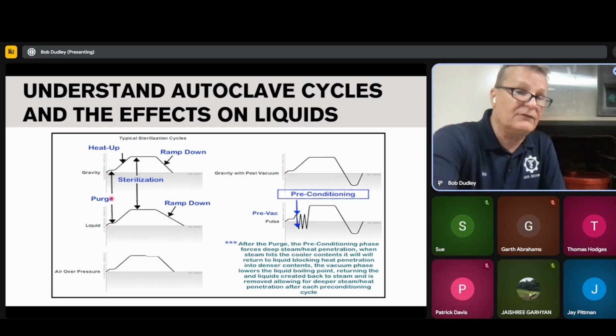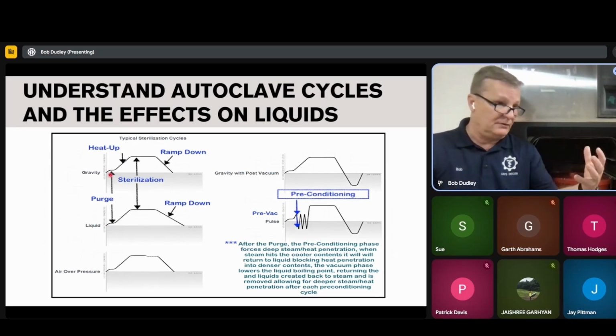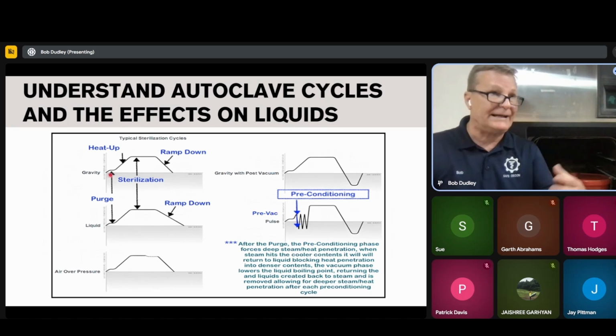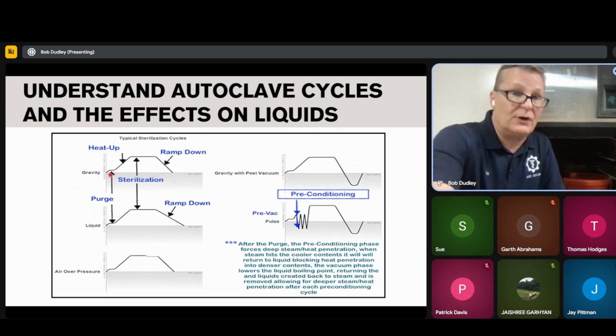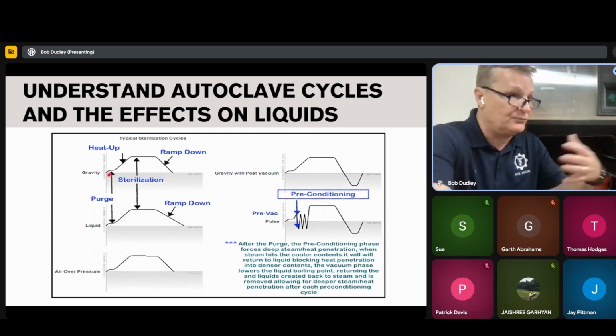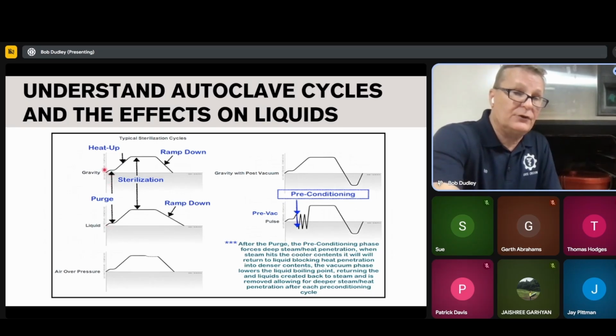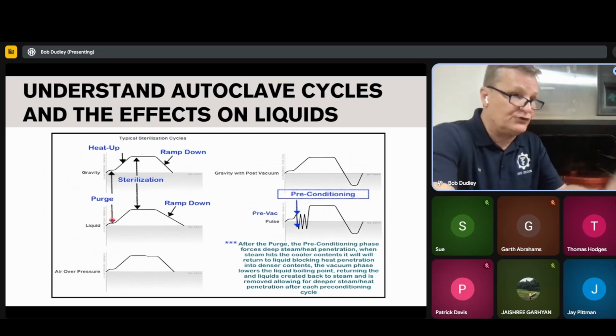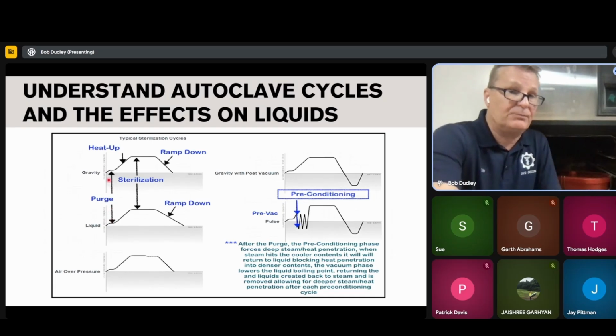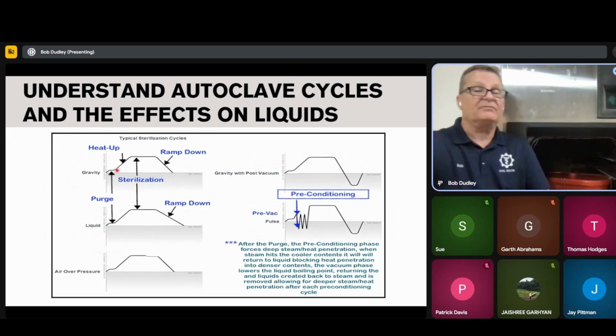So the whole idea of the purge is to create turmoil within the chamber, and it also starts preheating whatever you have inside that you're trying to get warmed up. So when it goes through the purge, it's preheating the chamber, the drain. It just preheats the pipes. It preheats every part of the cold area of that chamber, and then it'll level off, and then you get your heat up. Now, if you look at the gravity and the liquid, they ramp up kind of slowly, and they have to do this for a reason, as opposed to over here at pre-vac where it's straight up and down. They do this for a reason.